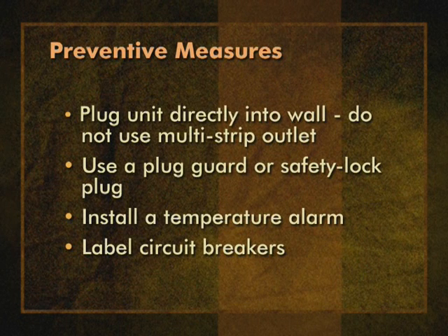Multi-strip outlets should not be used. Your refrigerator and freezer storage units should have plug guards or safety lock plugs so that they cannot be inadvertently pulled out. You may want to install a temperature alarm to alert staff to after-hours emergencies, particularly if large vaccine inventories are maintained.